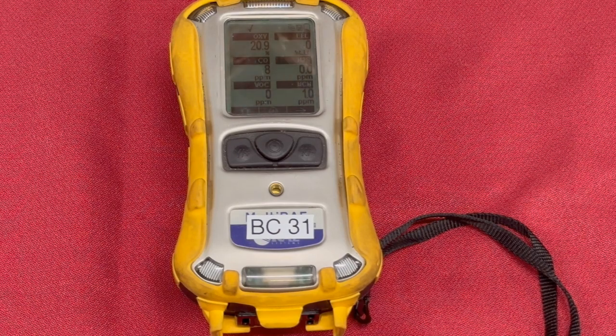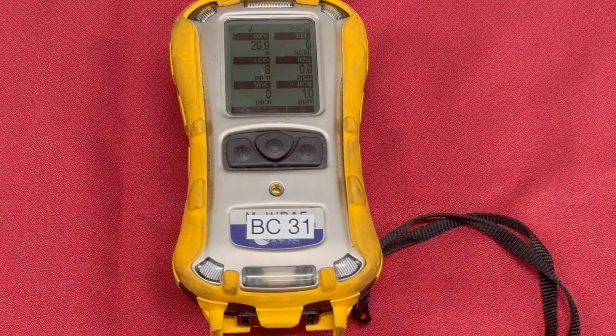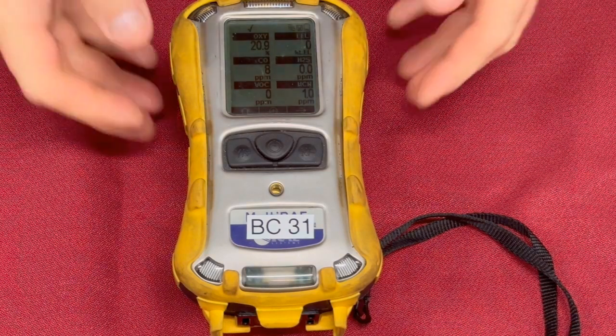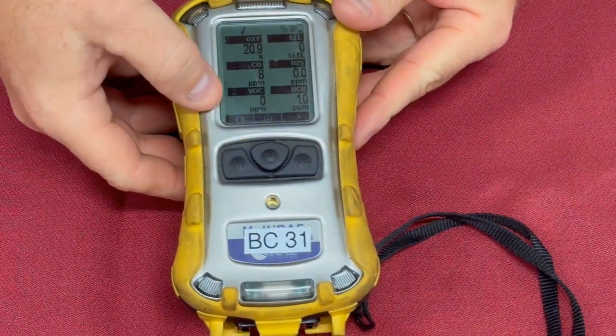And remember, this is the slow soak sensor. It takes about 2 to 3 minutes for it to get where it's going to go and level off. So when you use this at a structure fire, make sure you slow down and give that sensor time to adjust. The last thing down here says VOC.